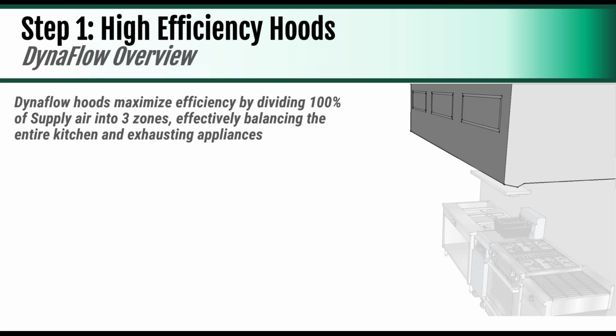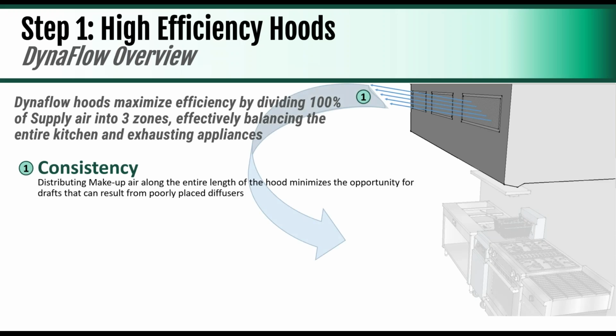The way that we're minimizing the exhaust volume is with our high efficiency hoods. So by minimizing the total exhaust volume as our first step, that allows us to typically find the cheapest energy savings with the quickest payback. Our Dynaflow hoods maximize efficiency by dividing supply air into 3 zones to balance the entire kitchen and exhausting appliances. The first zone is all about consistency. And those are diffusers at the front of the hood. They typically put out between 80 to 95% of the makeup air that's going in, just putting it into the room so it's consistently distributed so we don't have any drafts.